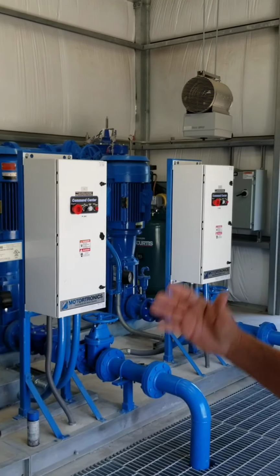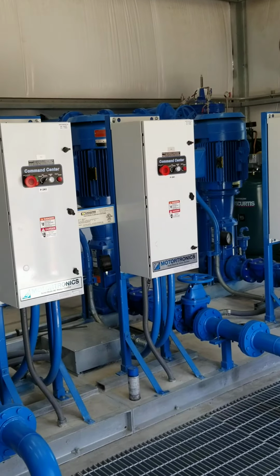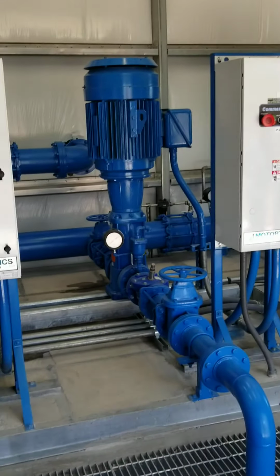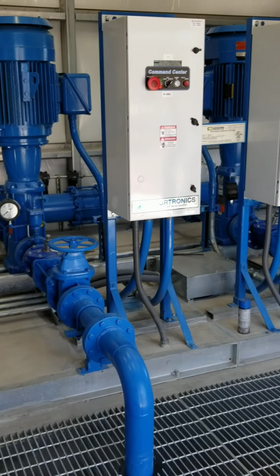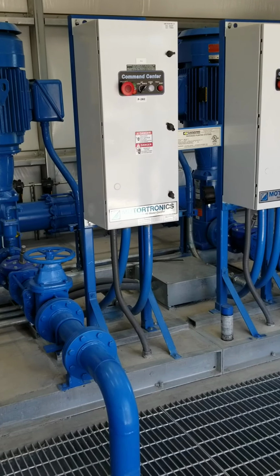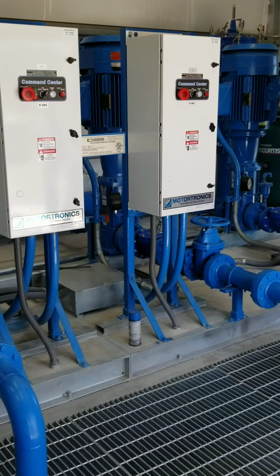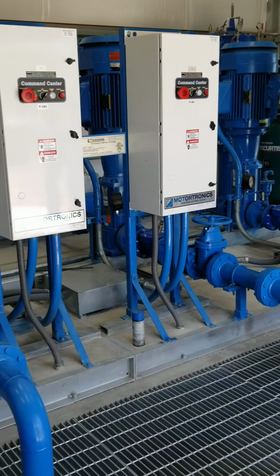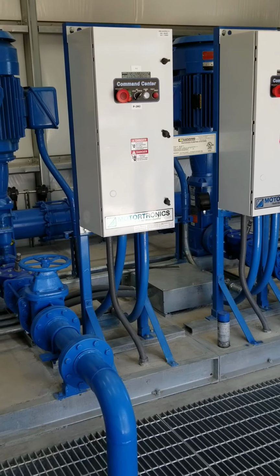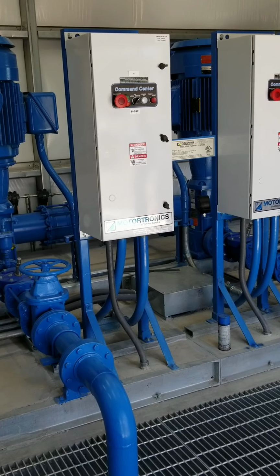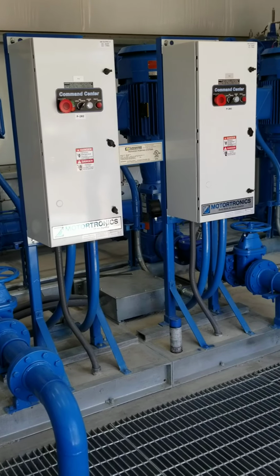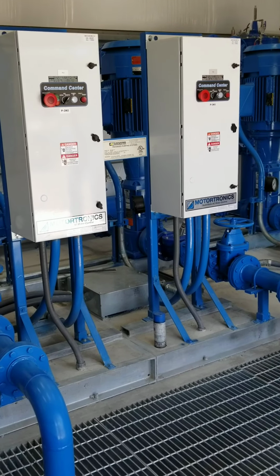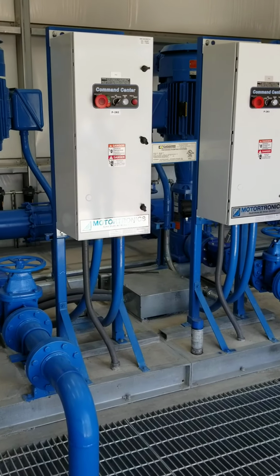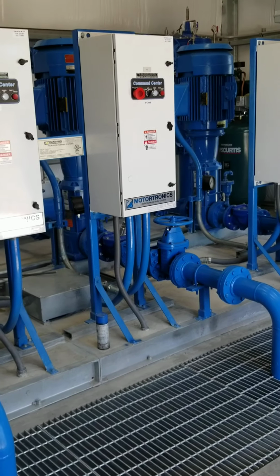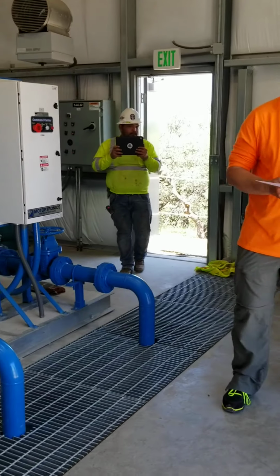They work independently. Well, he can tell you that. So we have two air compressors, and the air line from the air compressors goes to the hydro tank, and then from the controller, we're controlling each soft starter. We're monitoring the pressures and the air compressors. We're monitoring everything. We're even monitoring the chlorine out there. So that's an overview. And then, Bart, if you want to do the hydro tank, we'll take over from there.